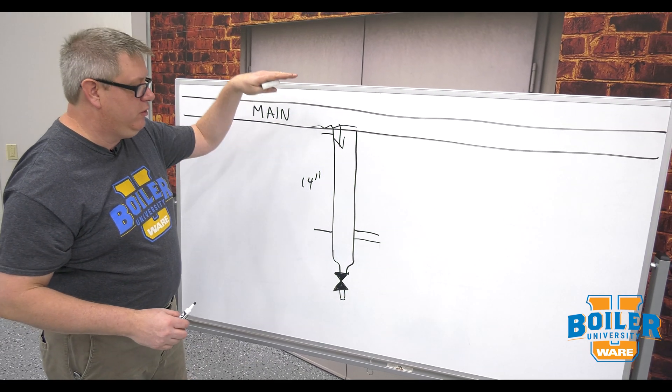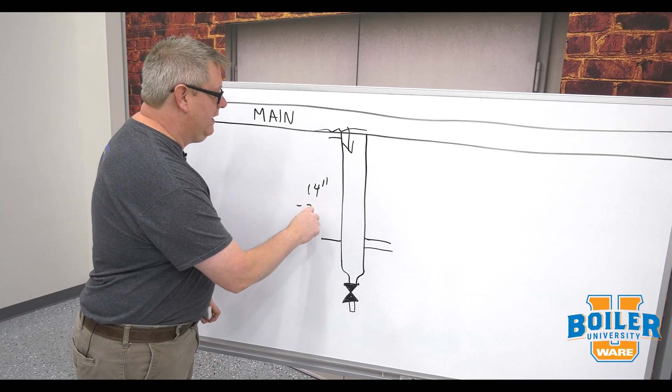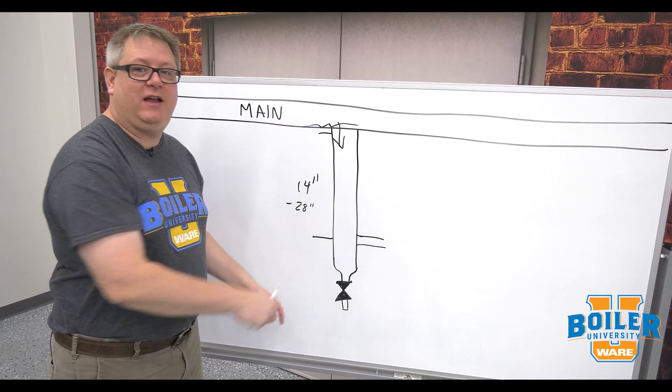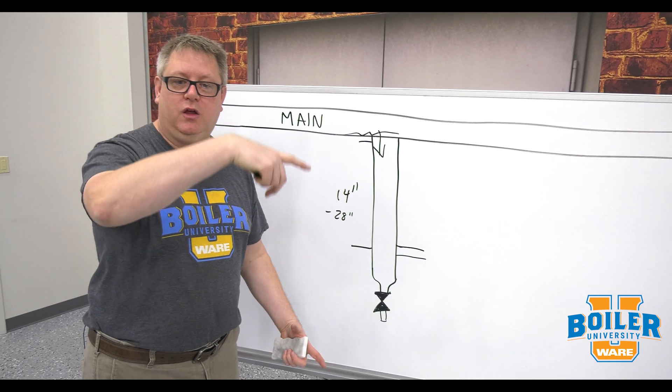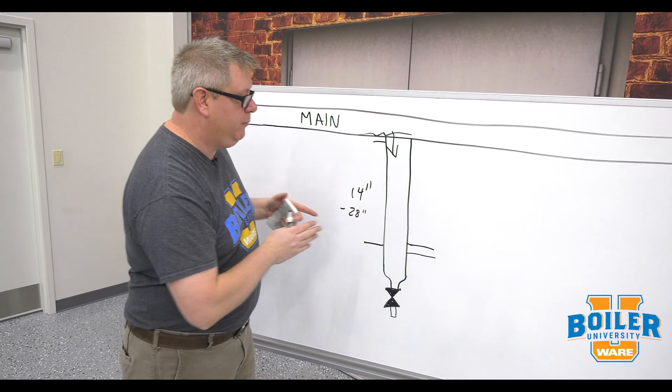In an automatic system where we want to do it all without any operator intervention we'll use a 28 inch drip leg and that just gives us additional volume to accumulate condensate until we get the system pressure to push it through our trap.